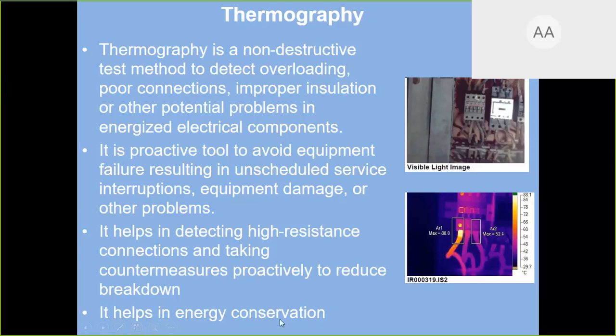It helps in energy conservation also, because I am not doing any overloading or improper insulation, and it will save electricity also, it will save my fire also, it will save spark also, it will save my overcurrent running. Then after doing thermography, we have to do the balancing of the load, which is very simple. Or if there is poor connection, you have to do the reconnection. So this camera, wherever you do the thermography, it will tell you in that area.